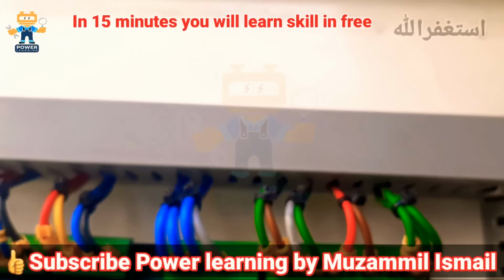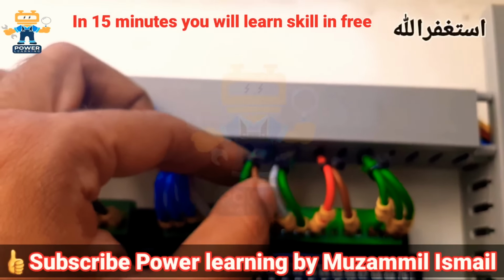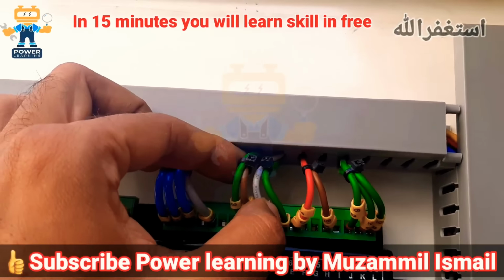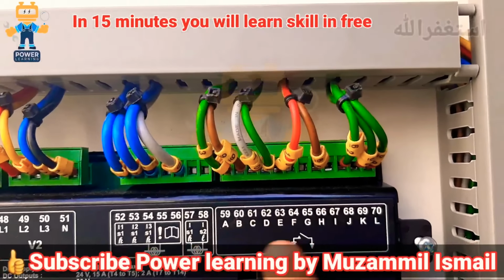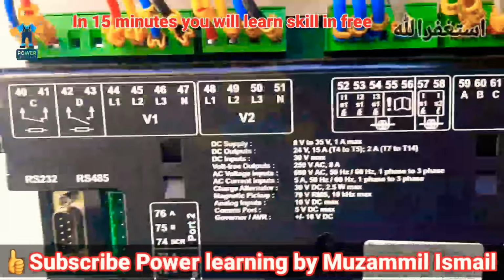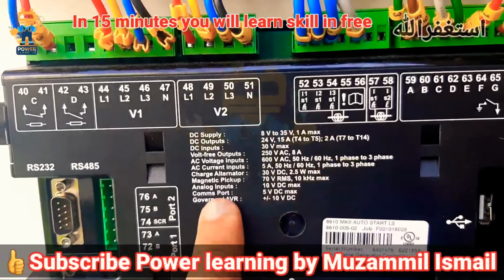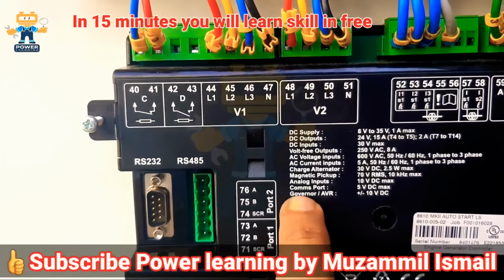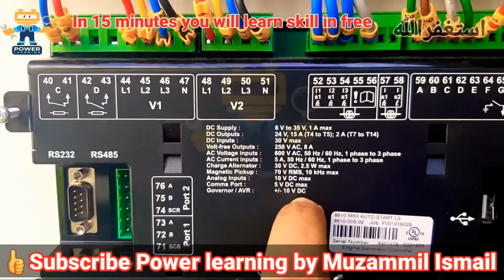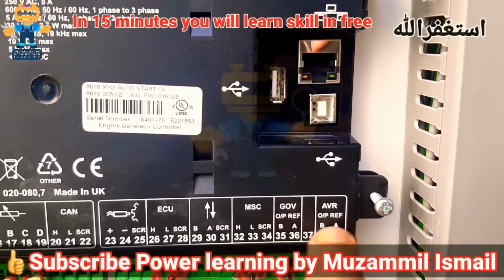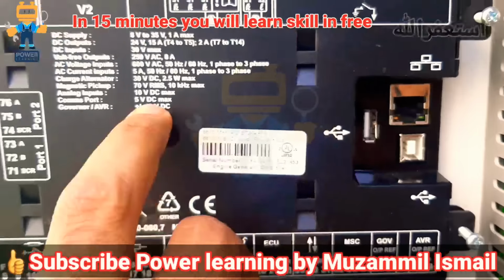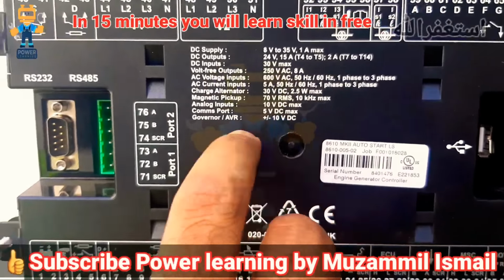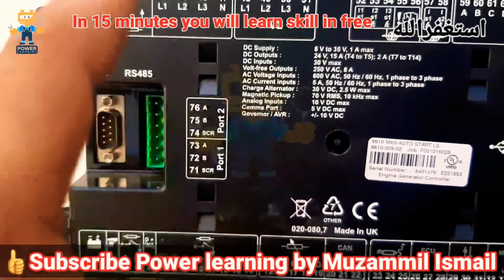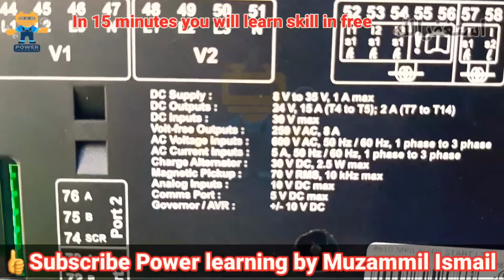Also, as you see, this is 62, this is 63 and 68 connected here, and all other inputs are connected here for different alarms like remote start, oil pressure switch, temperature switch. All switches you can connect on these digital inputs. Okay, these are the specifications of the controller. Governor AVR plus minus 10 volt DC, which I explained here. Okay, on these two terminals it is giving plus minus 10 volt DC. Okay, and others are mentioned here, you can see very clearly.